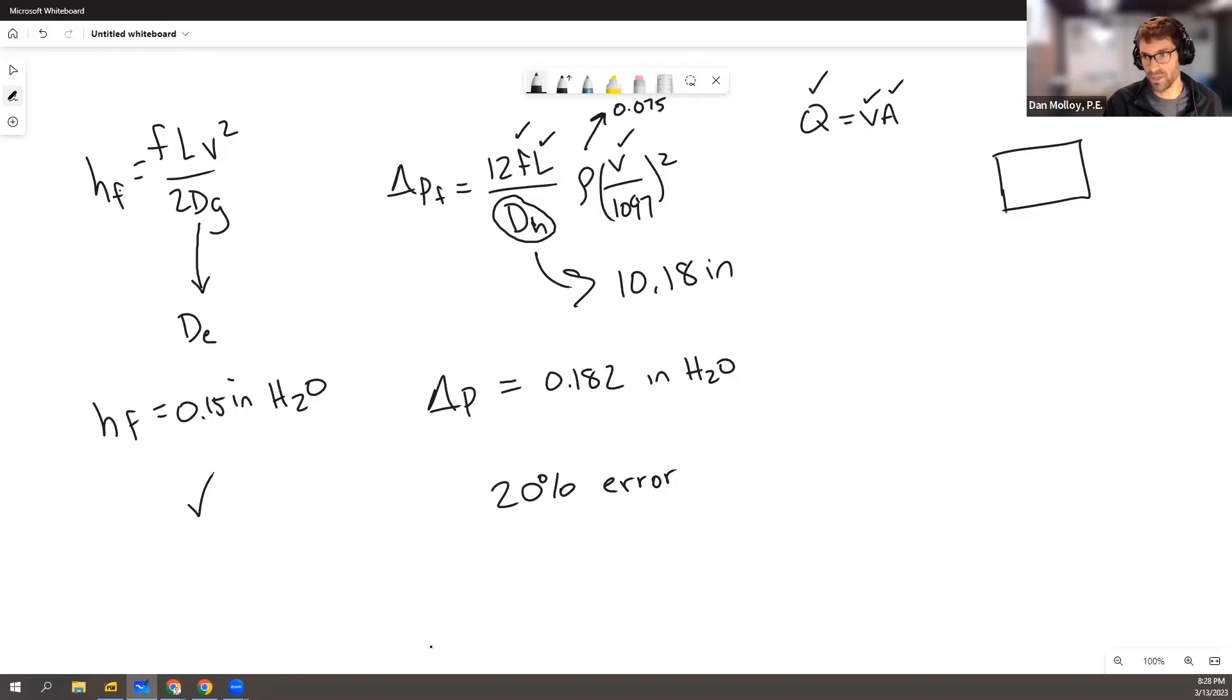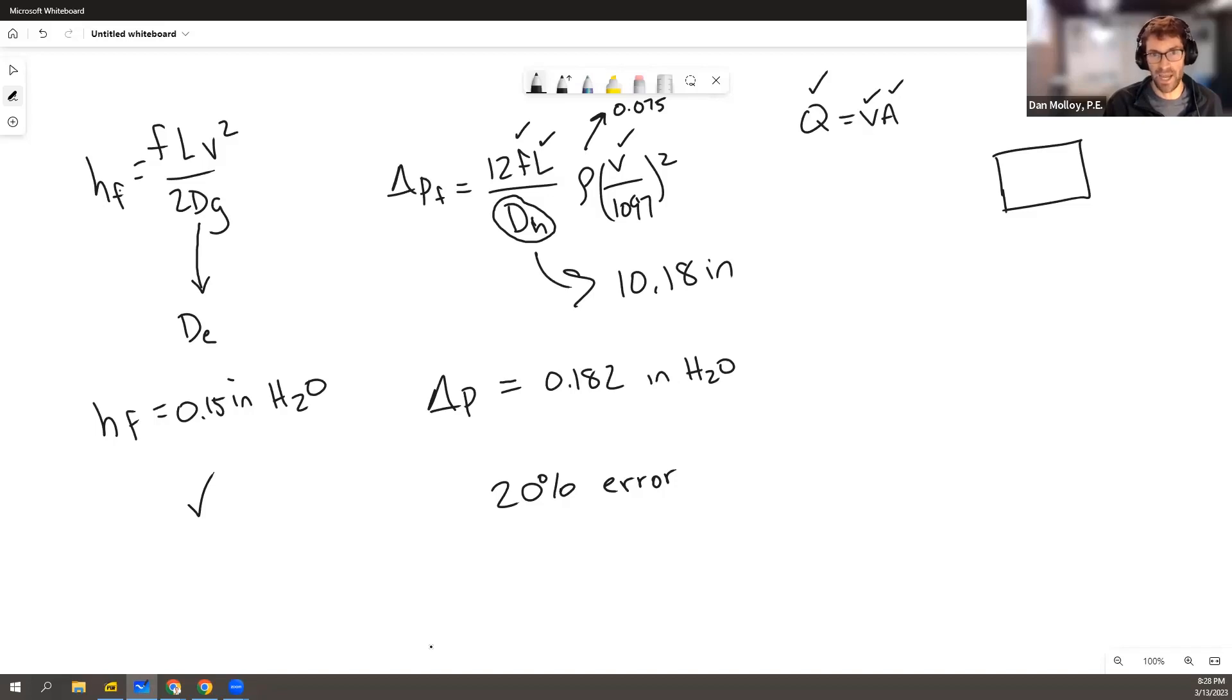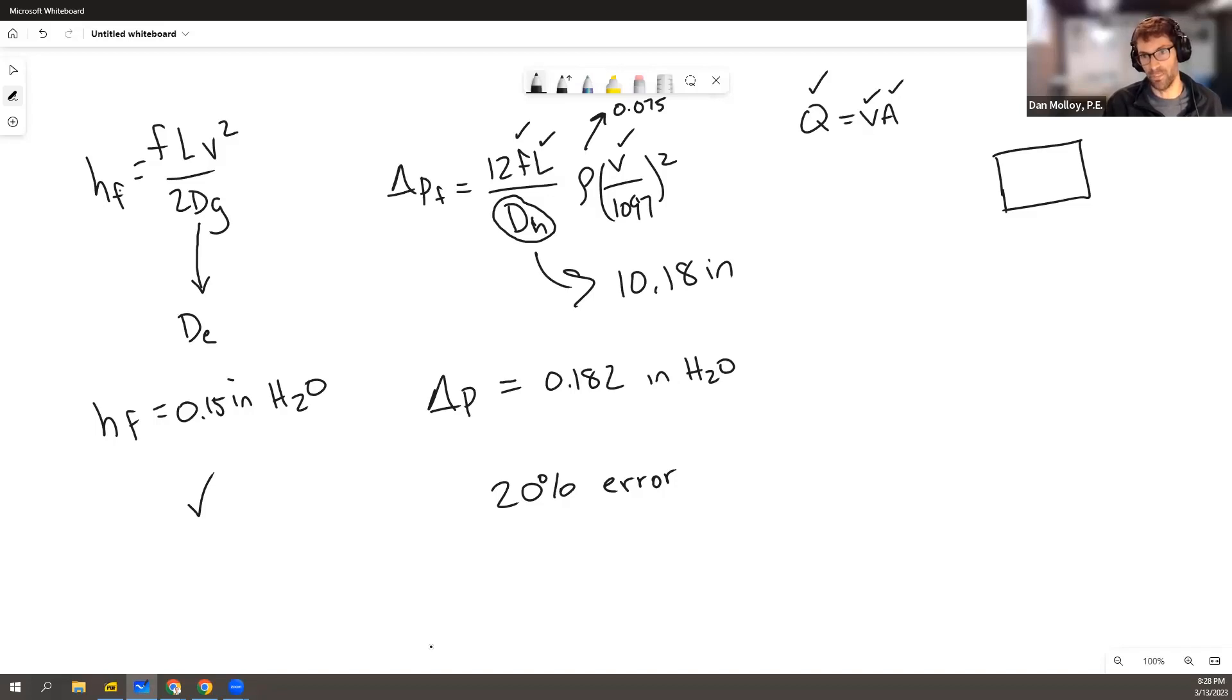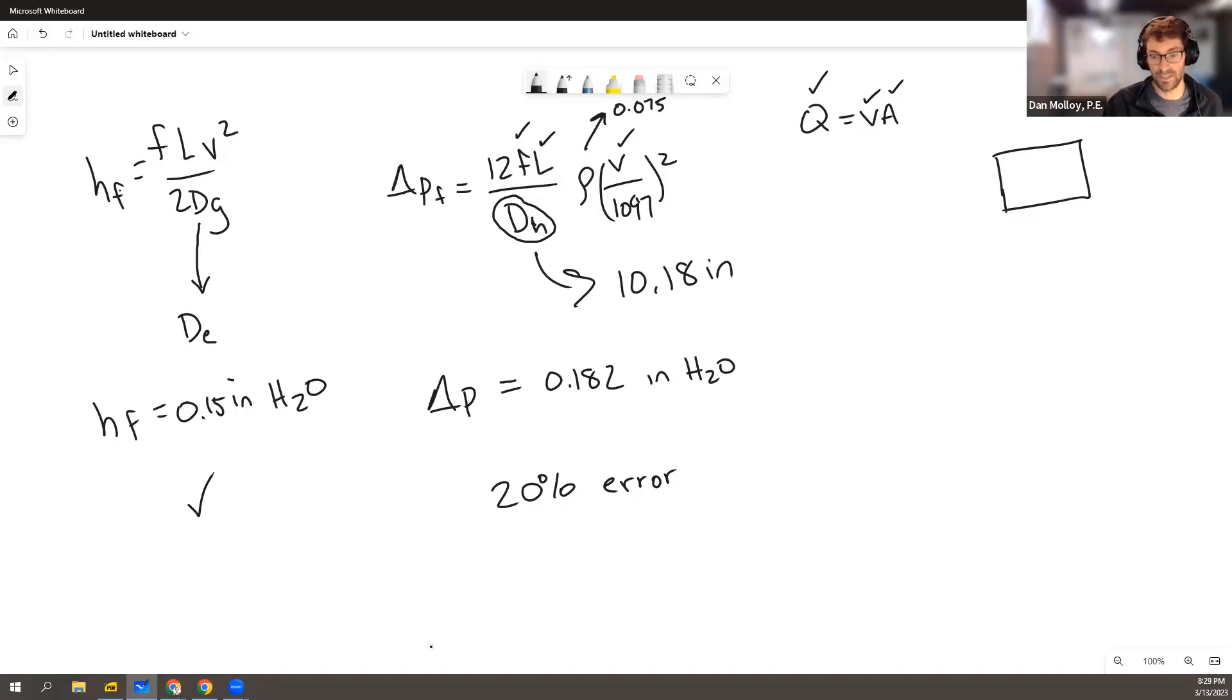I would think of a conduit is generally something smaller. But I think it's interesting that it comes out kind of close. And I think, again, all of the other numbers in here, this you have to carry all the units and figure it out and do unit conversions along the way. This is more of a rule of thumb approach. But like I said, they'll both get you to the same place if you use the same diameter. But this calls for the hydraulic diameter and this, in my opinion, should use the duct diameter if it's a non-circular duct.